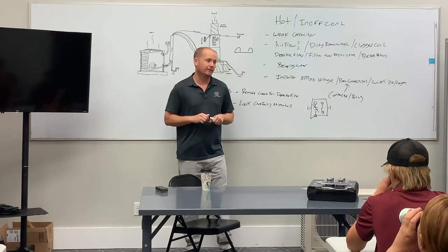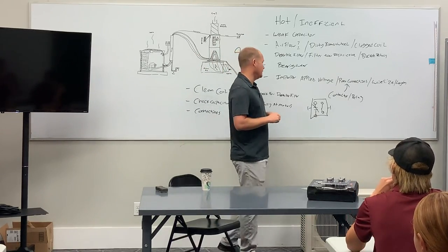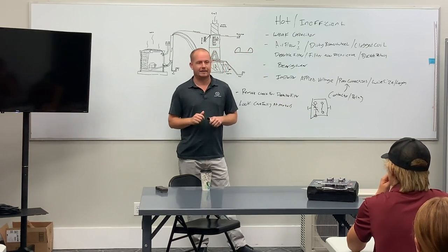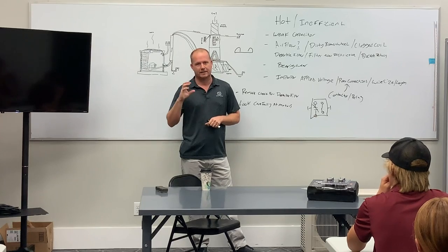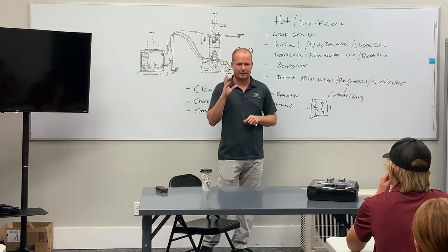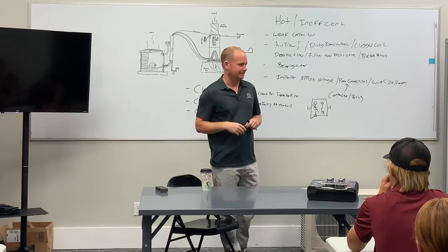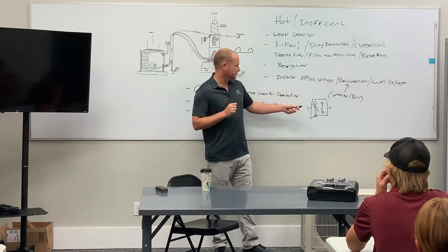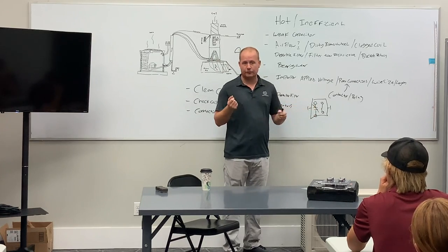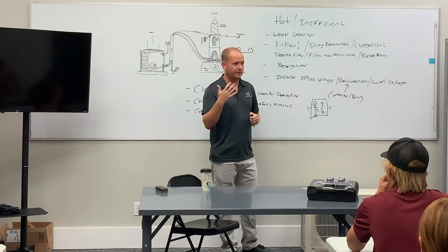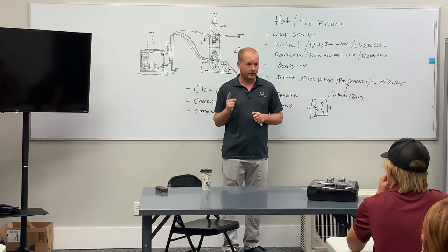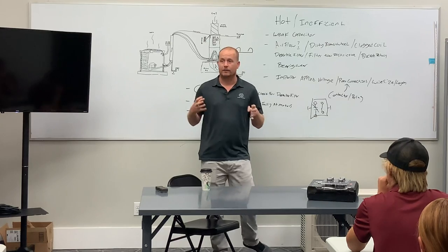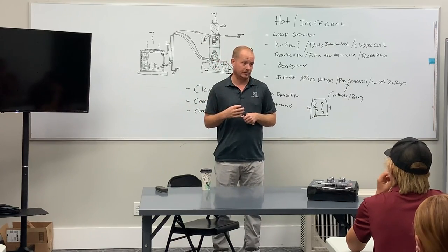Now, some people have thought that maybe there's some correlation between contact failure and the fact that it attracts insects. I think it's just the actual coil itself. There's something about the electromagnetic field that attracts insects. I'm really not sure why that is. But that's kind of another thing. As a side note, if you ever have a customer that has even one occurrence of insect-related failure, where ants got in it or whatever, go ahead and quote them to replace it with a sealed contactor.